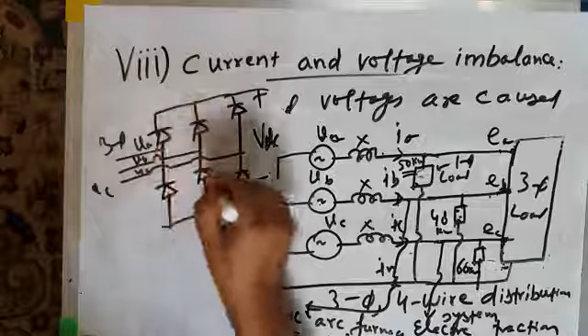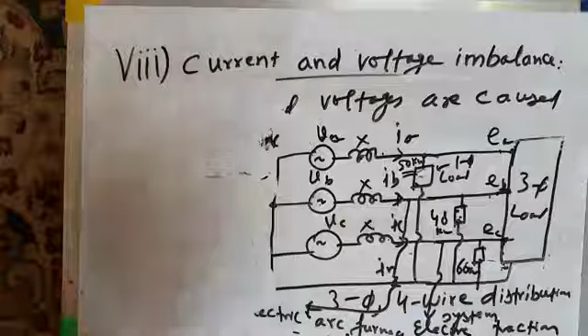Another problem is that if you have a three-phase bridge rectifier, so this is your three-phase bridge rectifier, which converts three-phase AC into DC. This is DC, VDC. This is three-phase AC. If these voltages VA, VB and VC are unbalanced, even a small unbalance in the voltages will cause large current drawing by this rectifier. The rectifier will draw large currents even if there is a small unbalance in the voltages, and that may burn the devices. These power diodes may get damaged because of large current. So these are the drawbacks of three-phase unbalanced voltages.